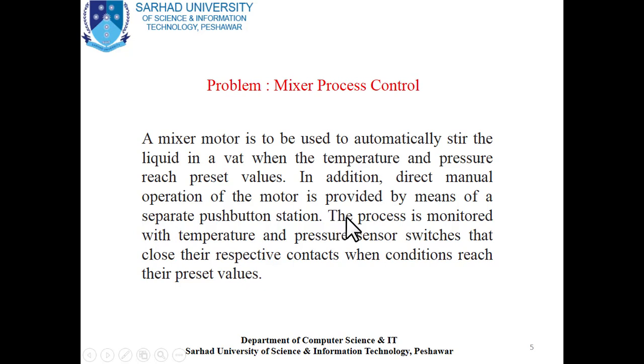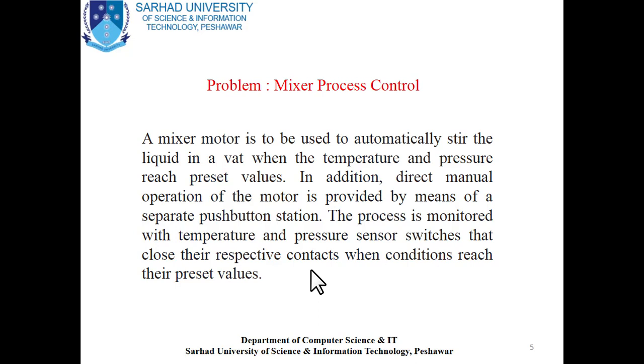The second portion is that we can control the mixer motor by a direct manual push button station. If we press the push button, the motor will start and stir the liquid in the vat. The process is monitored with temperature and pressure sensor switches, which close their respective contacts — which may be normally open or normally closed — when the conditions reach their preset values. The schematic diagram uses a mixer motor, temperature sensor, pressure sensor, and push button station.